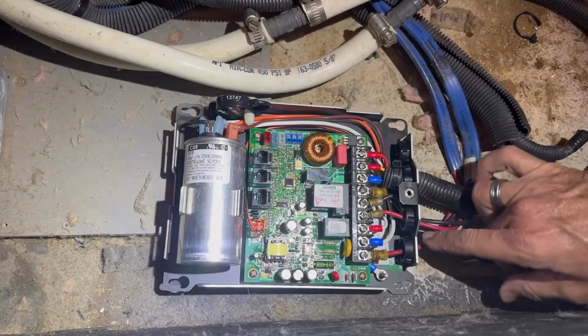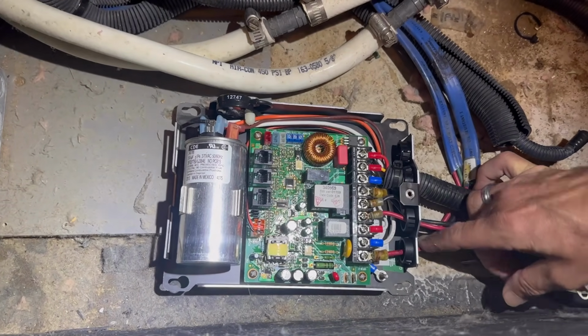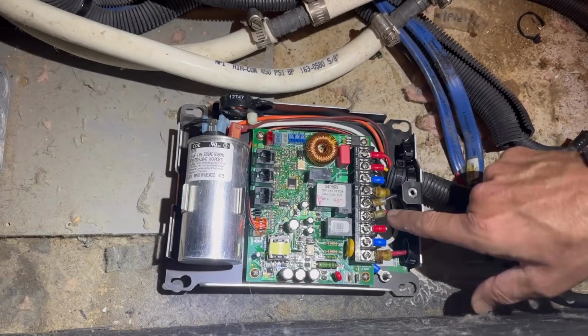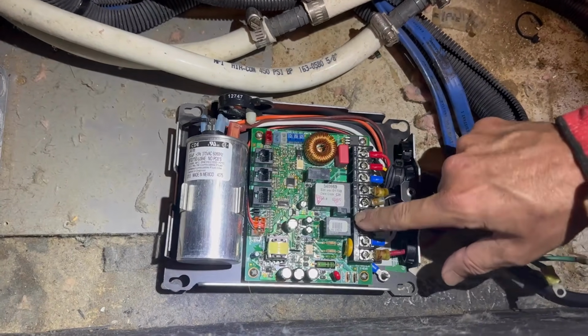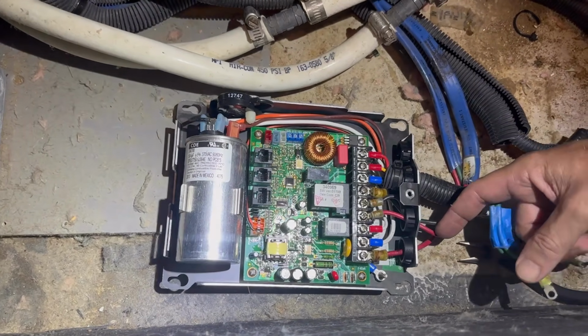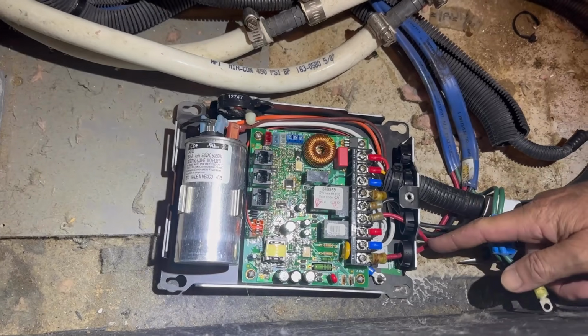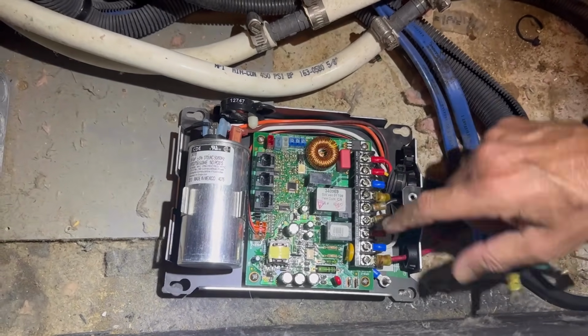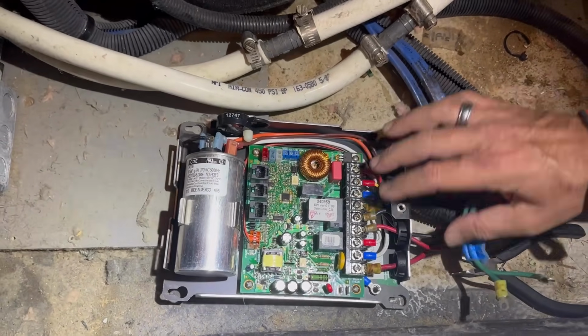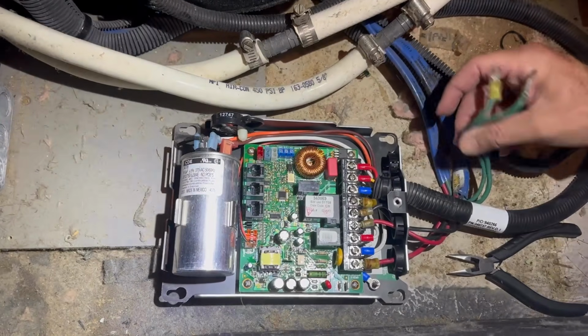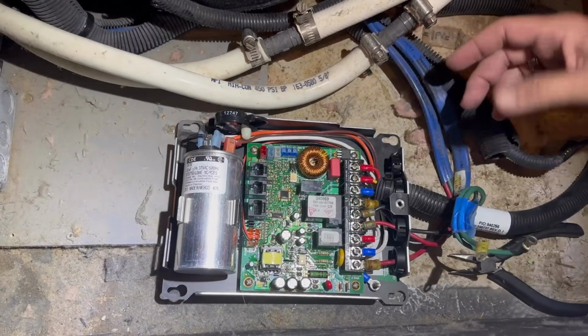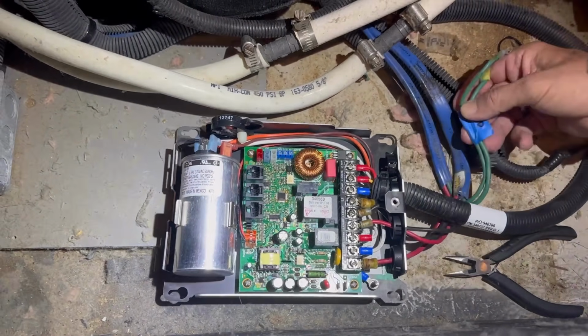So we want to take a blue piece of tape, put it right on here and write L2. Then we want to take this red wire and go to L2 pump, so we'll identify this one as L2 pump. And then the two black ones, the same thing - we're going to go to L1 and L1 pump on this. I'm going to do these right now - disconnect everything, mark them all, and then I'll show you what it looks like once they're all marked.